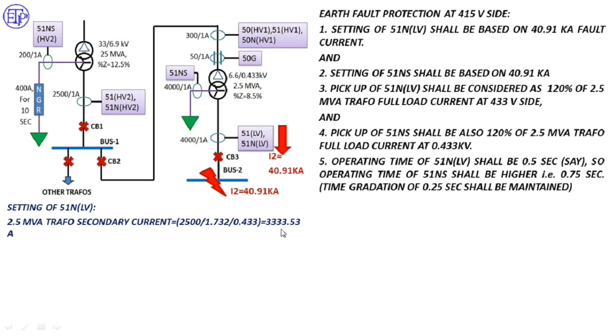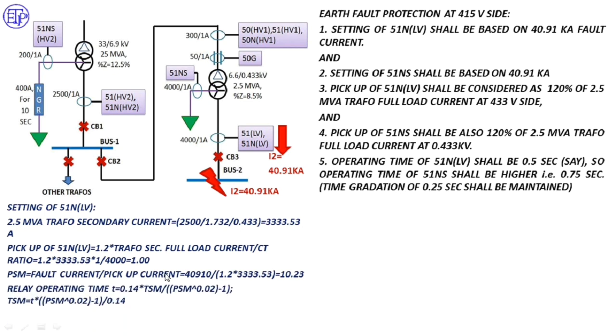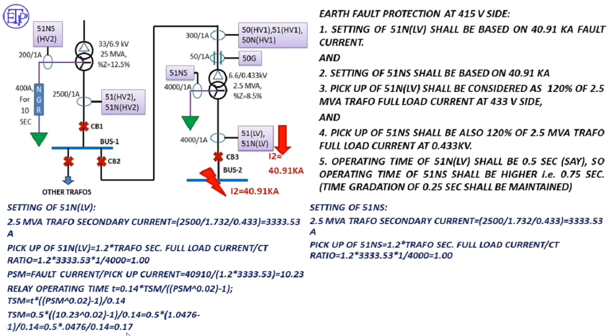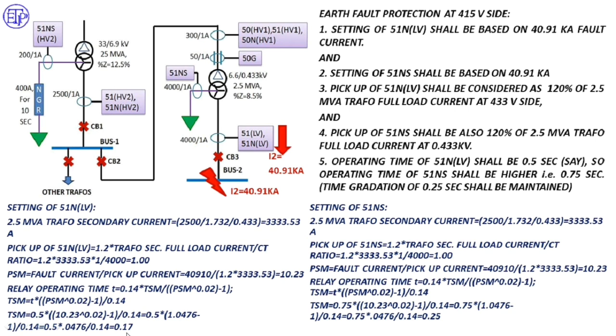Settings of 51NLV: pickup is 120% of transformer full load secondary current of 3333.53 A, divided by CT ratio of 1, giving a pickup of 1. PSM is calculated as 10.23. Based on a relay operating time of 0.5 seconds, TSM is found as 0.17. So this relay is set with pickup = 1 and TSM = 0.17. For 51NS, pickup is similarly 120% of transformer secondary full load current divided by CT ratio, giving pickup = 1, PSM = 10.23, relay operating time = 0.75 seconds, and TSM = 0.25.